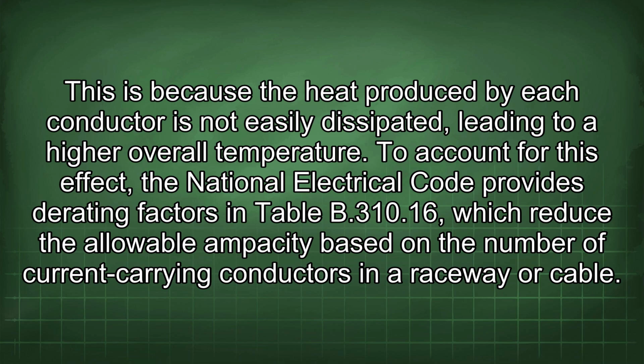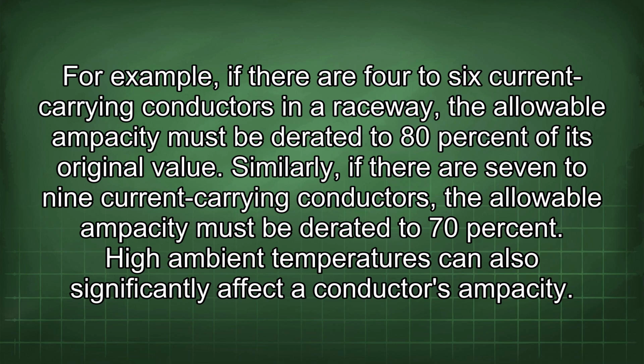To account for this effect, the National Electrical Code provides derating factors in Table B 310.16, which reduce the allowable ampacity based on the number of current-carrying conductors in a raceway or cable. For example, if there are 4 to 6 current-carrying conductors in a raceway, the allowable ampacity must be derated to 80% of its original value. Similarly, if there are 7 to 9 current-carrying conductors, the allowable ampacity must be derated to 70%.